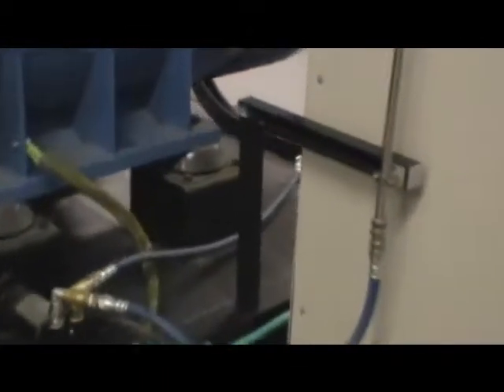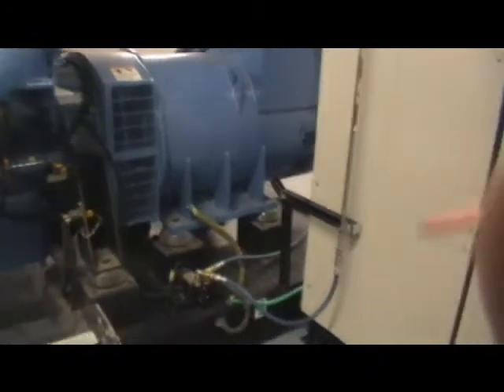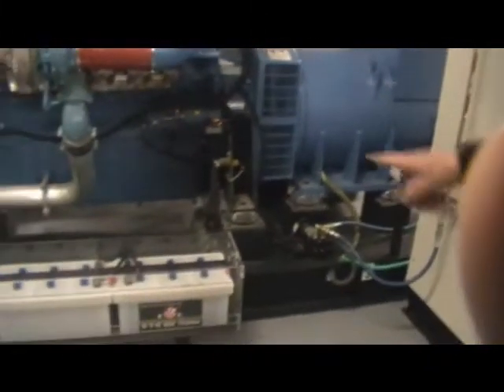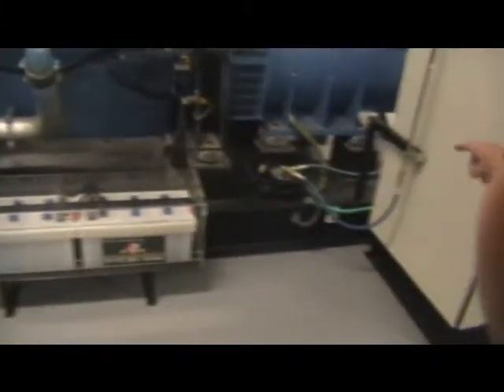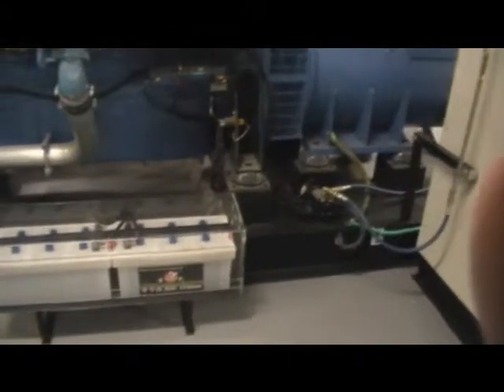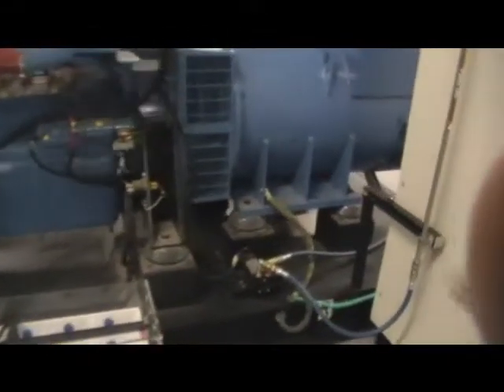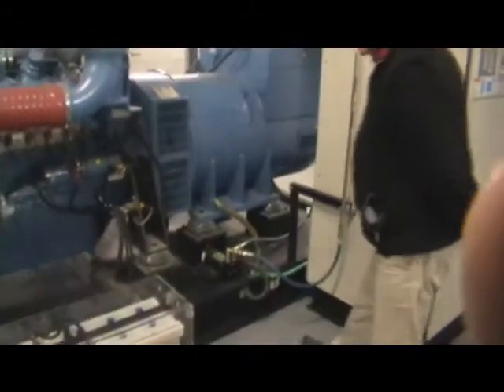So all this hydraulic stuff we're seeing here, what have we got going on? Are these fuel pumps? Fuel pumps, yes. You've got an incoming fuel line, lots of filtering, and there's a day tank in the base of the generator. That's why I saw a tank inlet on the other side. Yeah, this is just drawing it from the main tank into here, and that's a 24 volt DC fuel pump off the batteries.